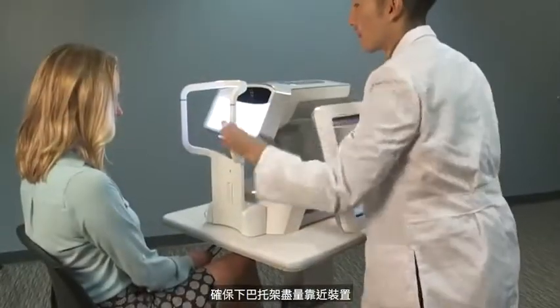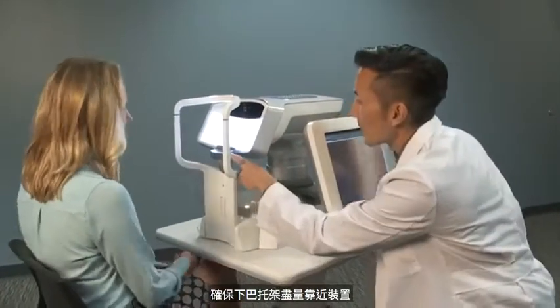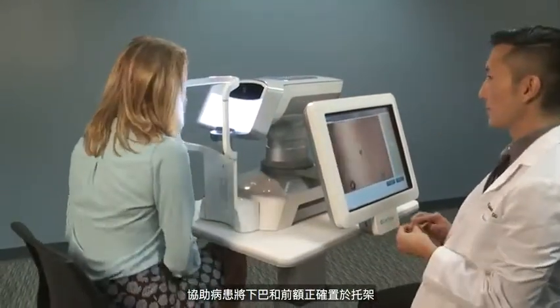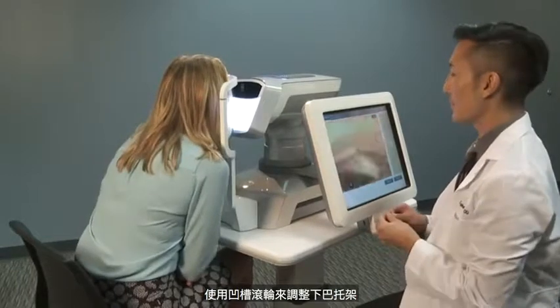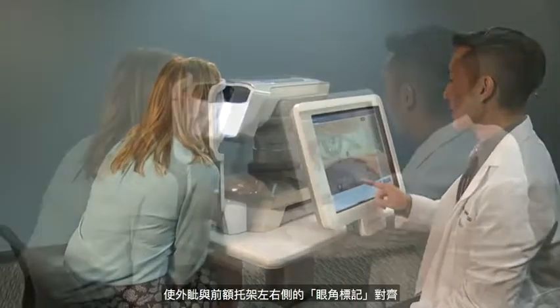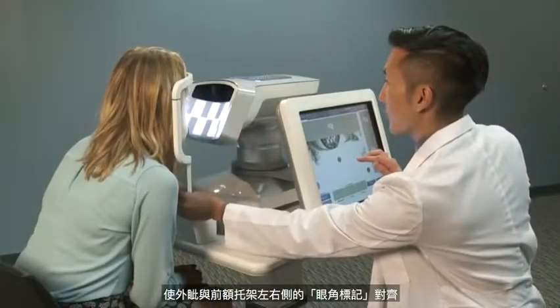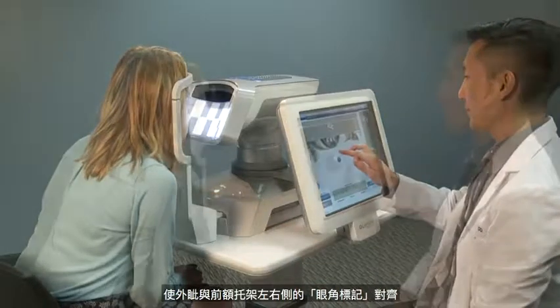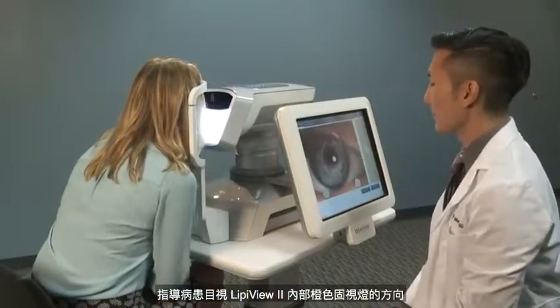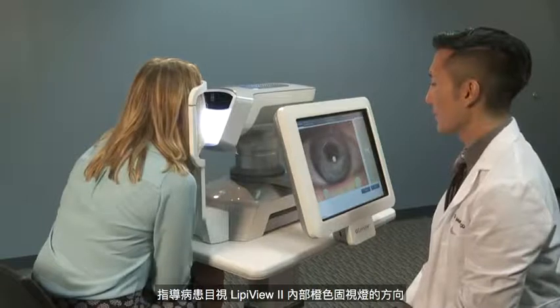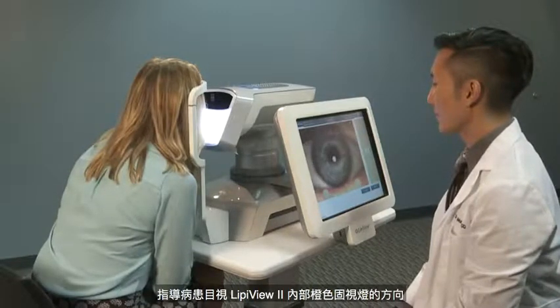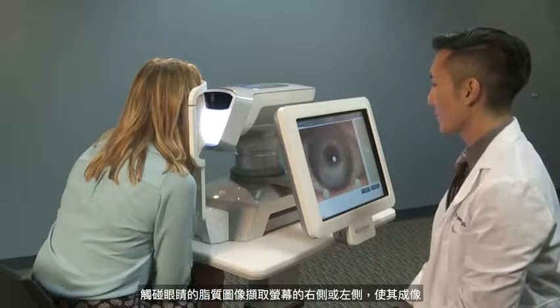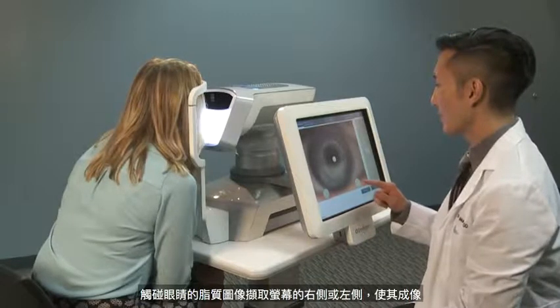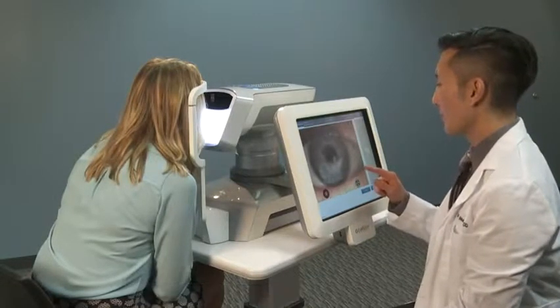Ensure the chin rest is in the closest position toward the device. Position the patient properly into the chin and forehead rest. Adjust the chin rest with the fluted roller to ensure the temporal canthus is aligned with the marks on the right and left side of the forehead rest. Instruct the patient to look in the direction of the orange fixation light inside the LipiView 2. Touch the right or left side of the lipid image capture screen for the eye to be imaged.